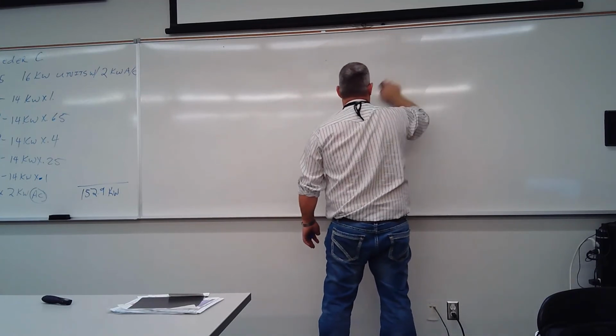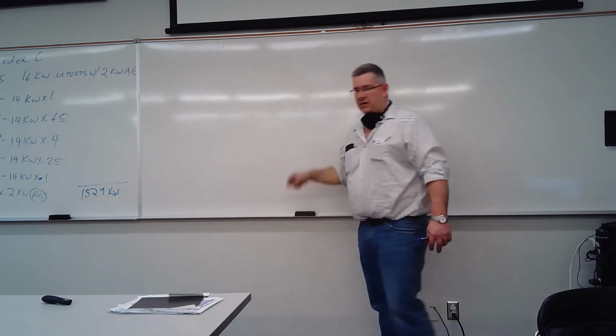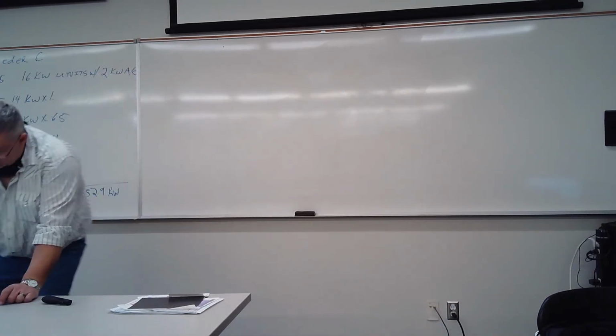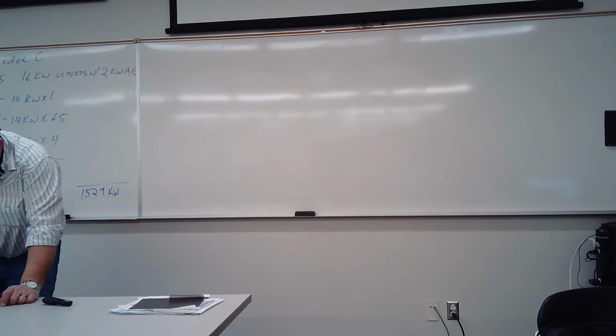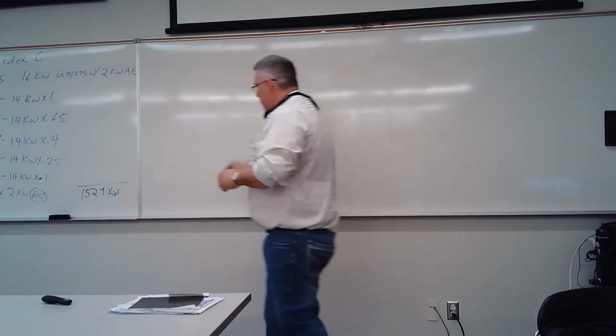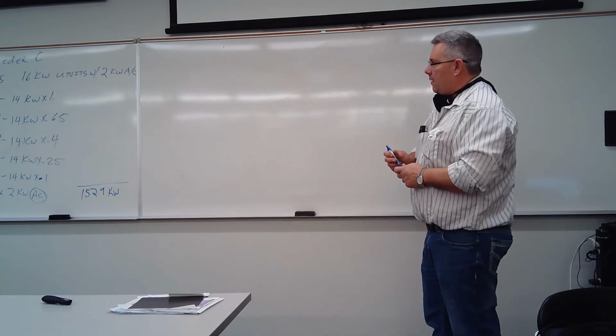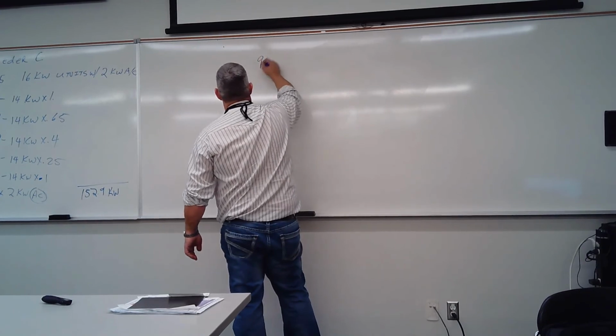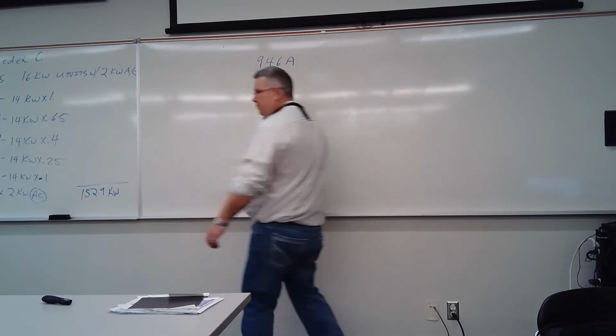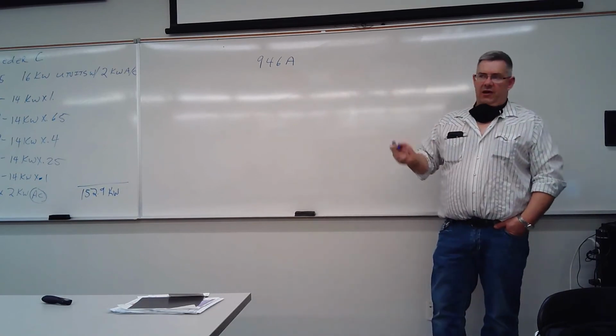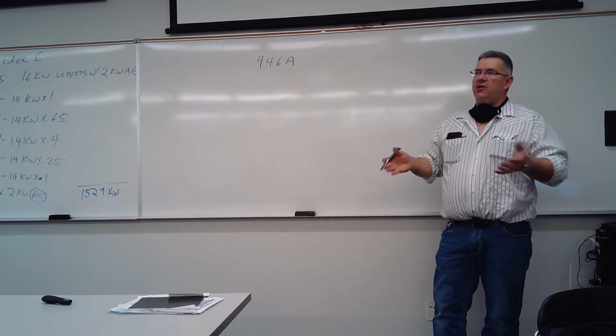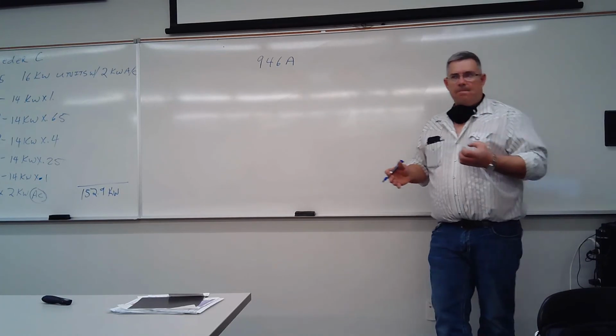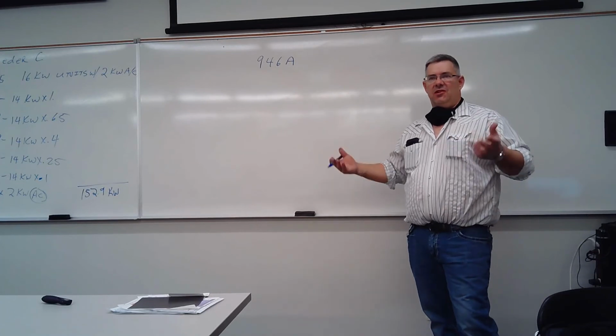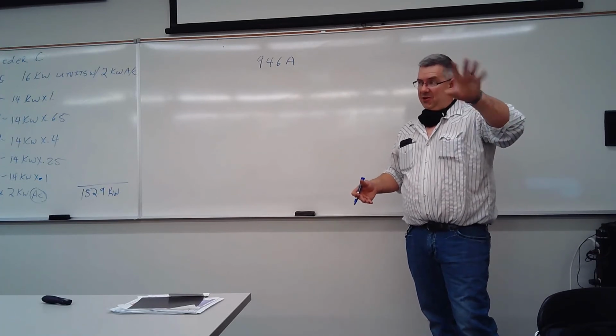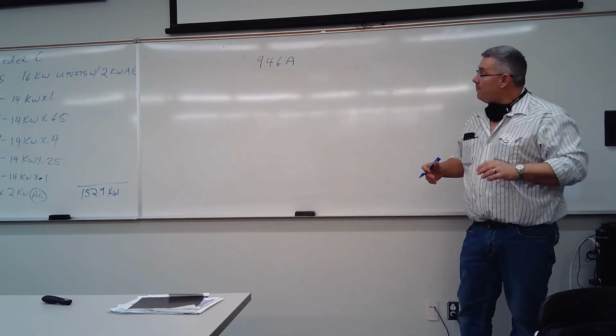when you go through, where is neutral conductors covered? Which code rule is that? This rule is 4-018. Okay. So it says you can reduce the neutral conductor. So coming into that building, we had an ampacity of 946 amps. Okay? So our line conductors have to be good for 946 amps. That's fine. If we wanted to, we could actually pull smaller neutral conductors because it's a three-phase system. This is beyond, but I'll show you just because it got brought up.